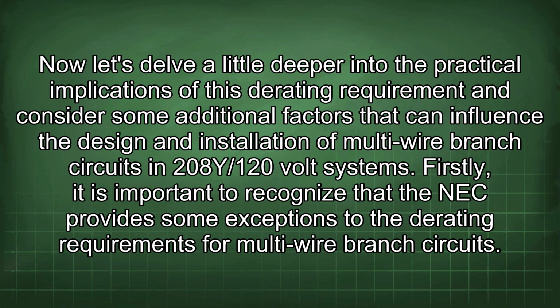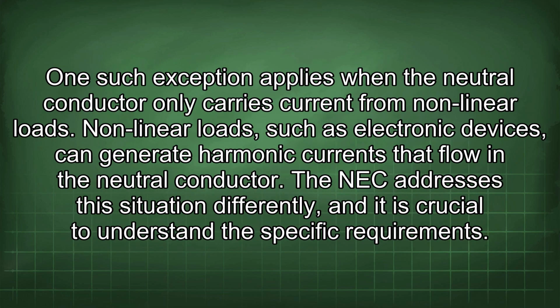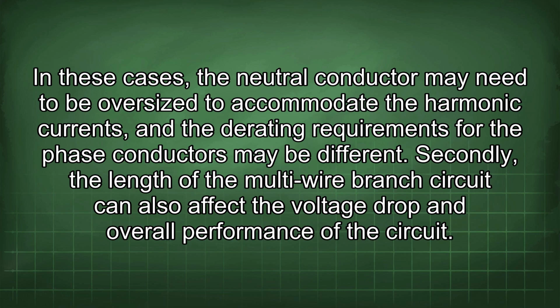Firstly, it is important to recognize that the NEC provides some exceptions to the derating requirements for multi-wire branch circuits. One such exception applies when the neutral conductor only carries current from nonlinear loads. Nonlinear loads, such as electronic devices, can generate harmonic currents that flow in the neutral conductor. The NEC addresses the situation differently, and it is crucial to understand the specific requirements. In these cases, the neutral conductor may need to be oversized to accommodate the harmonic currents, and the derating requirements for the phase conductors may be different.